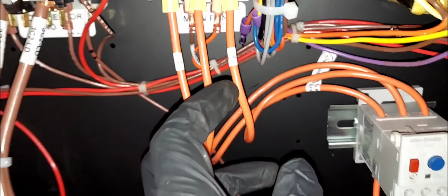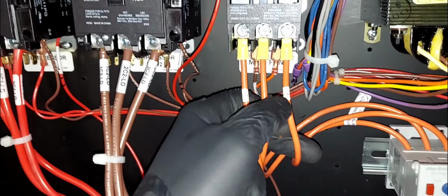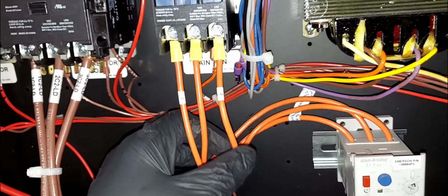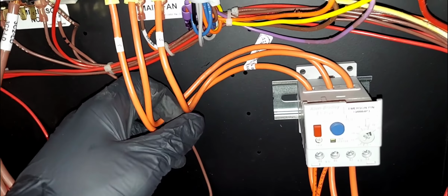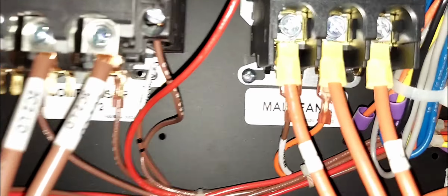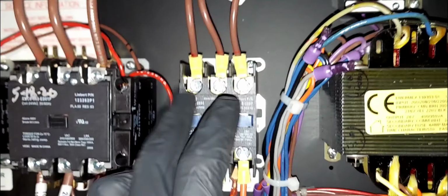Okay guys, I think right here this is the main fan overload. There's a main fan contactor. So on other versions of Liebert, they'll have an actual button on the motor. So I was assuming it was the same thing, but this right here is it. Main fan contactor, and this is the overload section, almost like a starter, but the contactor and the overload section are separate. So I'm going to assume that these two, this is the controls, low voltage, and I'm assuming that these are open right now. I'm going to grab my meter and I'm going to test it.